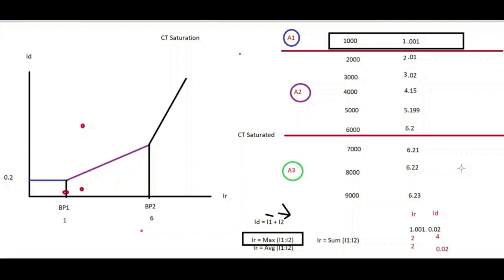So now let us understand how do we work for this. So when one CT, let us assume fault current is 8000 amps. One CT is reading 8 amps in secondary. Other CT is reading 6.22. Okay. Fault is external. What should happen? Your relay should not trip. Okay. So external fault, what will be your current? 8 amps, 6.22 amps. The fault is external. That means 8 minus 6.22. How much it is? 8 minus 6 is 2 amps. So 1 point some value. 1.8. Let's say 1.8. This is my differential current.